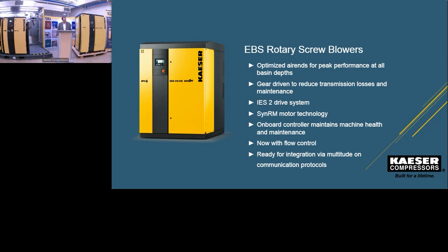Another interesting aspect of this unit is it is equipped with what we call a synchronous reluctance motor, or sometimes also referred to as a SynRM. Now, SynRM or synchronous reluctance motors are not new to the world. They've been around for as long as electric motors have been around, but they've had some issues in the past just getting them started. But with new technologies, and specifically VFD technologies, these motors are now coming back into favor, and what they offer is an improved efficiency over your traditional motor designs.